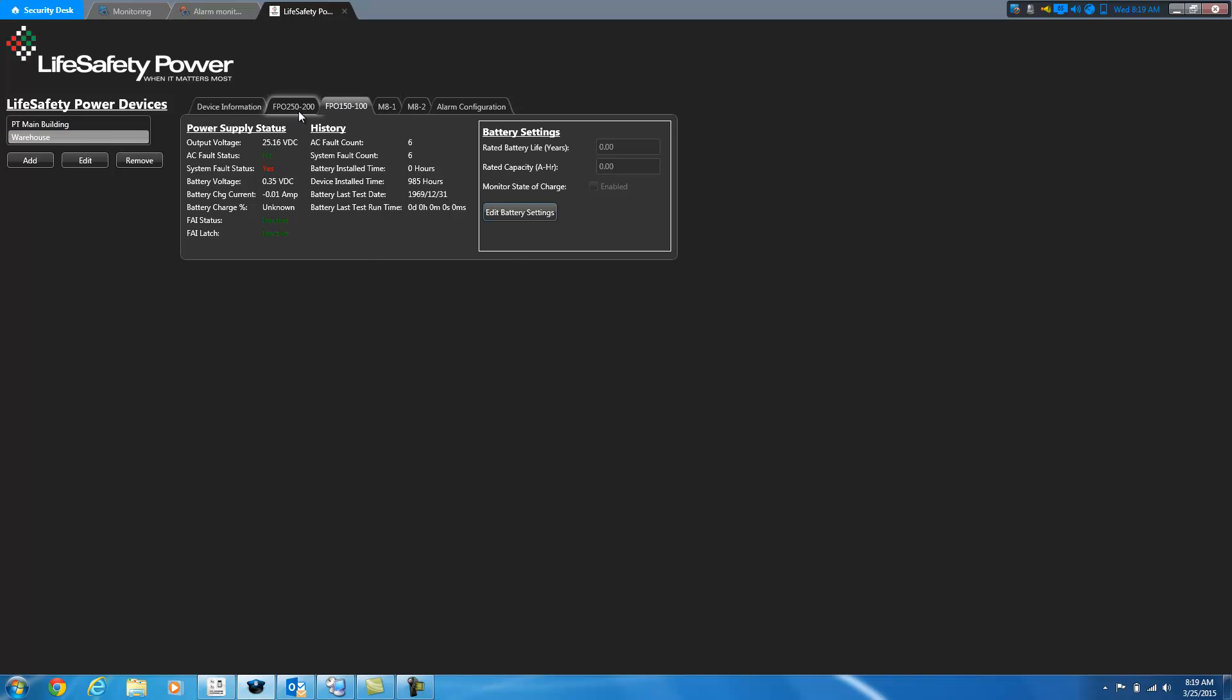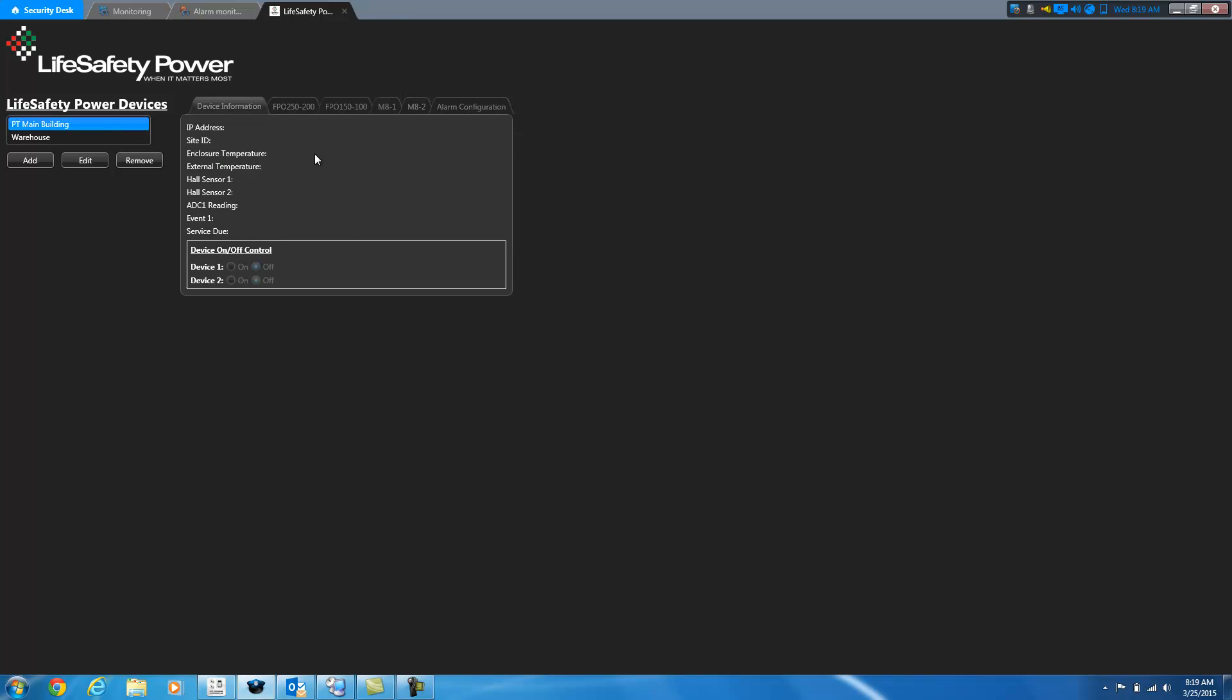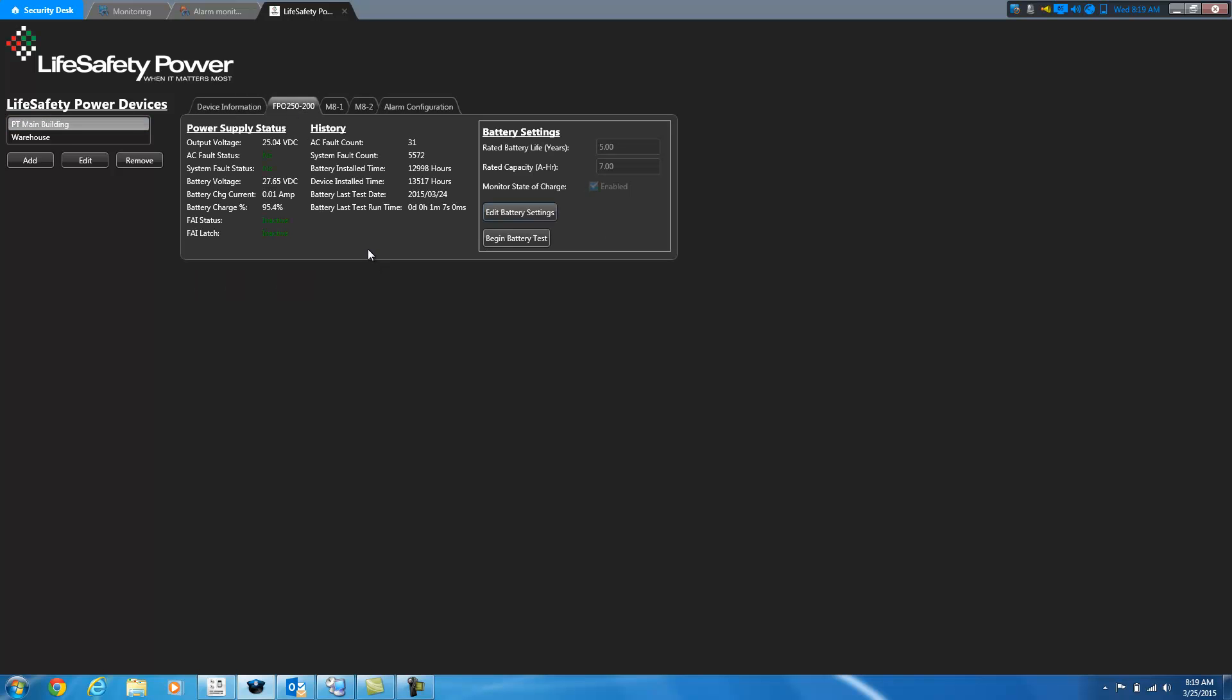So I'm going to go back to the other board. So this is the FPO board. So you can see on this FPO board that we're outputting at 25 volts. We don't have any AC fault statuses or system fault statuses. Our battery voltage is at 27 volts as well. We're currently sending a trickle charge down to the battery. It's at about 95% charge.